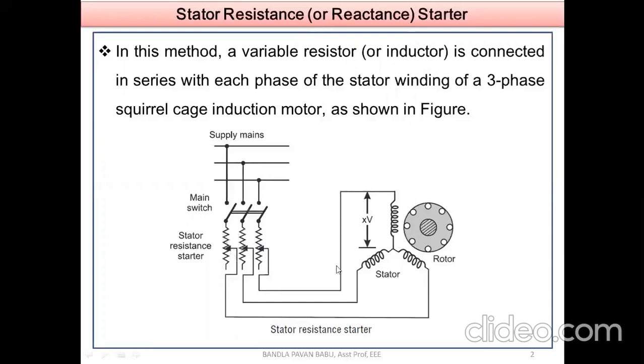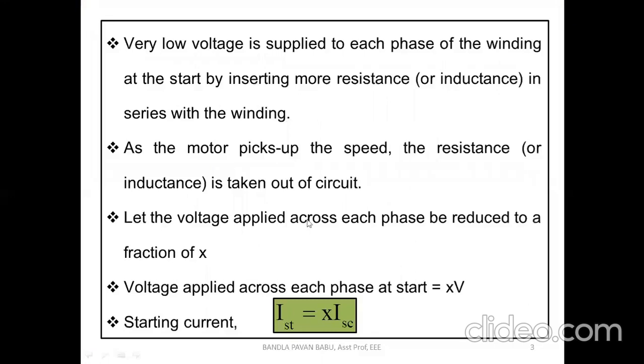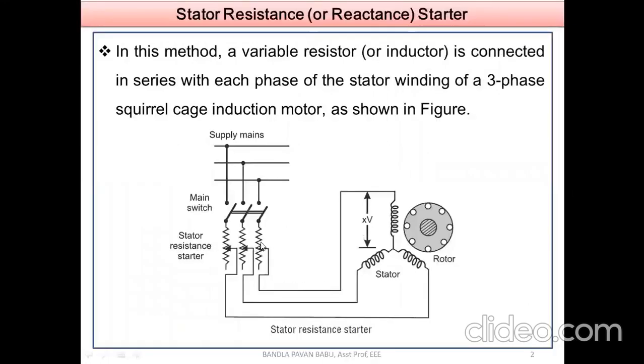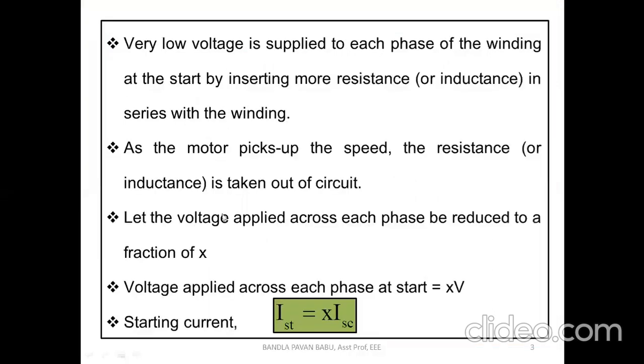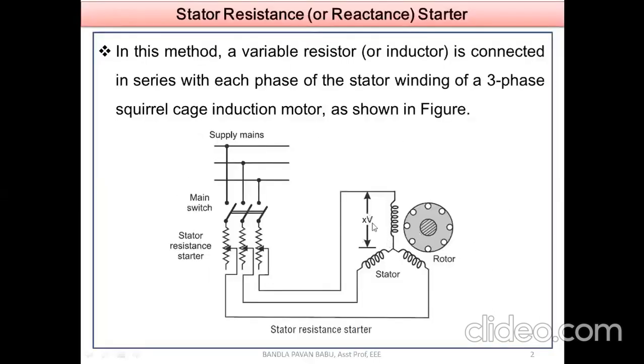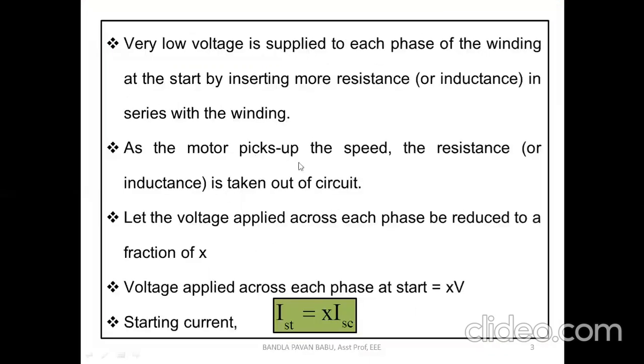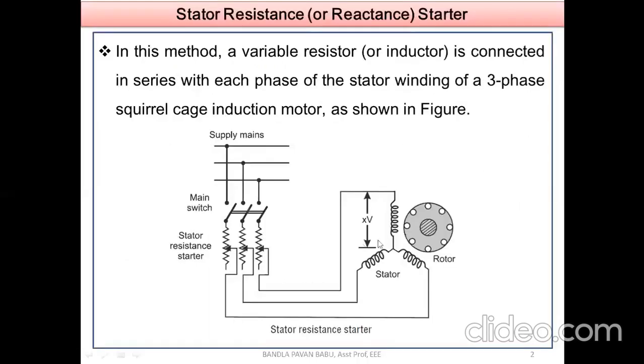Okay, so let us see. At starting, we are going to add the resistance in series at each phase. So what is the purpose of adding the resistance? We are going to regulate the current. That is the main thing. And obviously, at each phase the voltage is also getting varied. So let us see that ratio. I can call it X into V, where X is some constant or some ratio. So that means if you want to apply 90% or 80% or 70%, likewise. So 100% we are not applying the voltage.